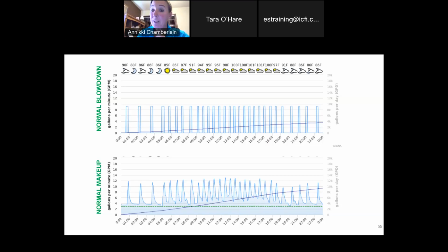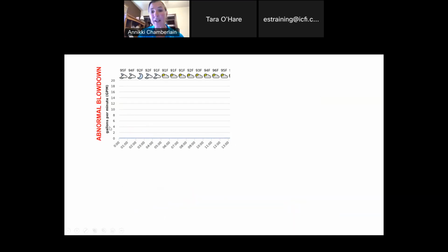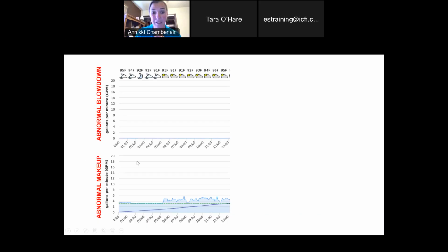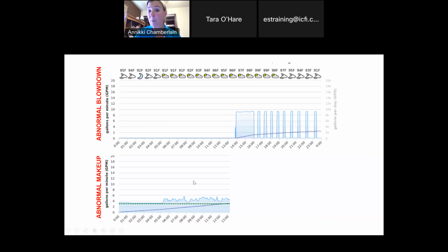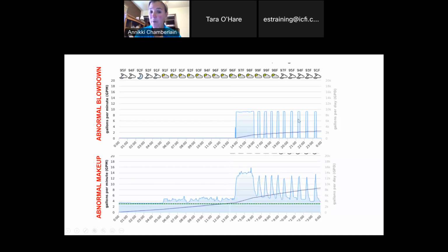So what happens if I see, oh my gosh, with 1 minute resolution, I'm like, whoa, I haven't blown down for 13 hours. That's crazy. I could either be having a water waste event where I'm overflowing, and so the chemistry is not getting high enough to blow down, or I could be having a stuck blowdown valve, and that's asset damage, right? I could be getting ready to scale up. So if I compare it to my makeup for the same amount of time, I see, oh my gosh, my makeup is not stuck on, so I know I'm having a scale event. I go out there, this operator did a manual blowdown, fixed the blowdown valve, we're back to normal operation. Same thing, the tower filled, and we're back to normal operation.